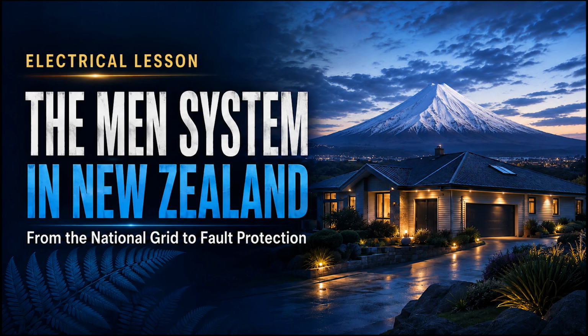A correct explanation is important, but an electrician must also prove that the real installation matches the explanation. This is where inspection and testing become essential. A diagram can look perfect, while a real connection is loose, corroded, missing, or connected to the wrong bar. That is why inspection and testing are essential. Before connection or after relevant work, the installation must be verified in accordance with the applicable requirements.